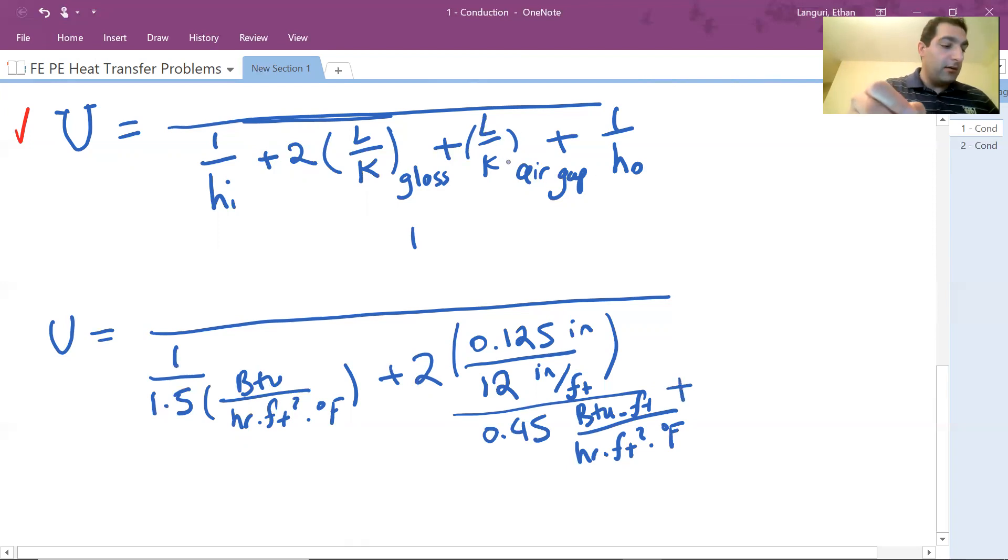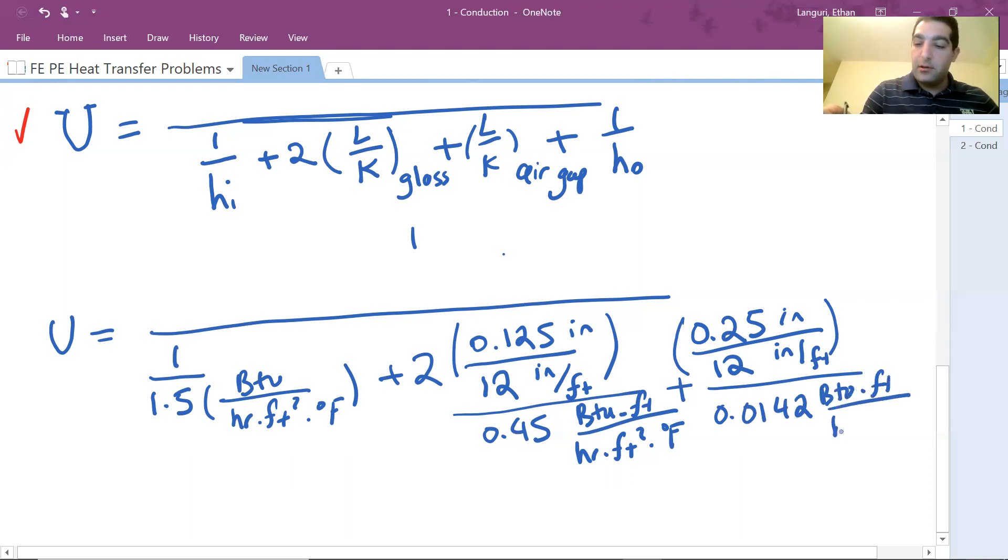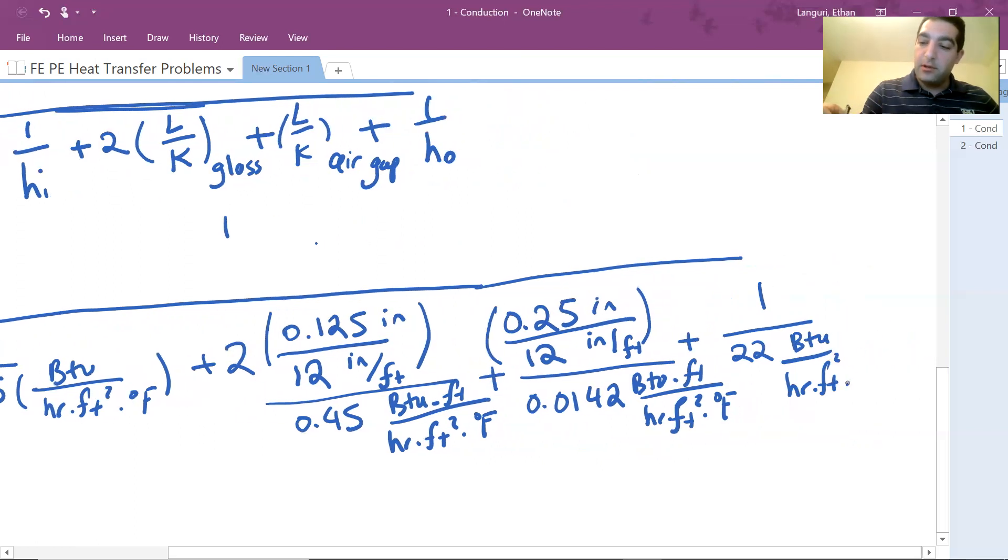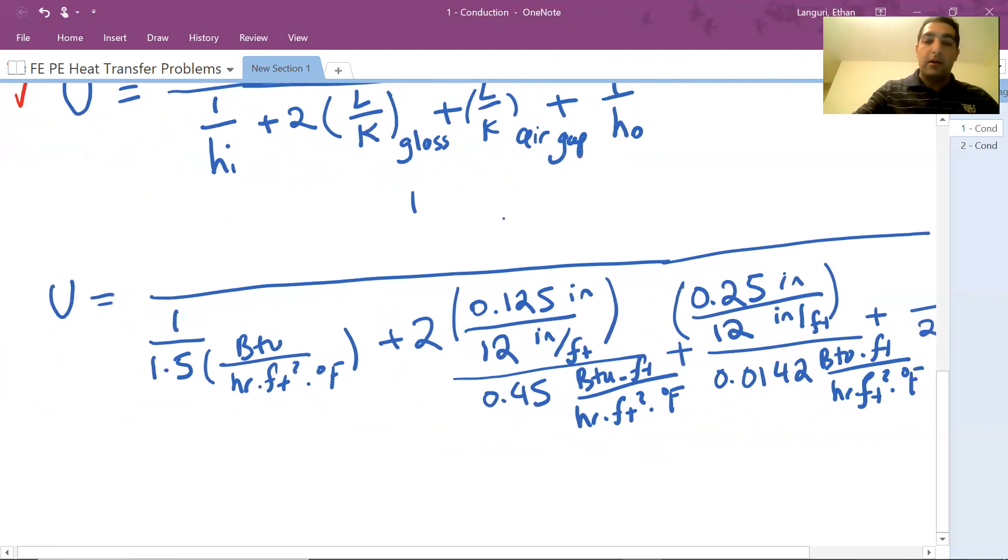And so this is 2L over K. K for glass we found to be 0.45 BTU foot per hour foot squared degree Fahrenheit. And I'm going to add L over K for air now. 1/4 inch, 0.25 inch, I'm going to divide it by 12. Since one foot is 12 inches, so I have L and then I have K of air, which is 0.0142. Let's write down the unit as well—BTU foot per hour foot squared degree F. And I have one more term to go, plus 1 over outside heat transfer coefficient, which is 22. So let's write down the unit: BTU per hour foot squared degree F. So this is my U.